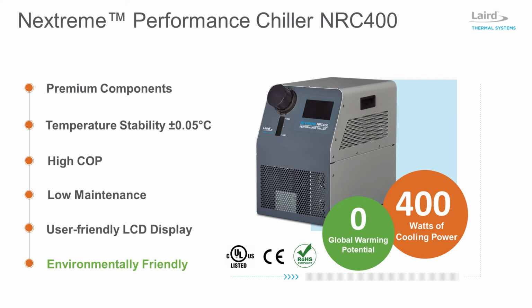The NRC400 is approved by UL for laboratory use per UL 61010-1, has CE marking, and is RoHS compliant. Thermoelectric-based chillers are environmentally friendly, as no harmful HFC refrigerants are used, resulting in zero global warming potential. The unit operates on a universal power supply, making it easy to source one part number for global use.